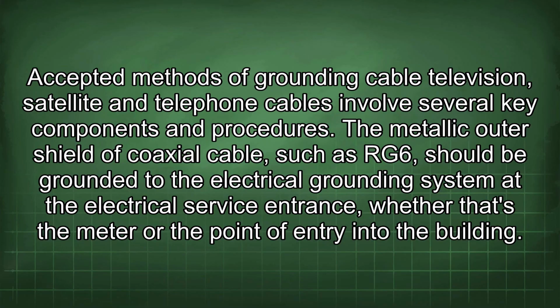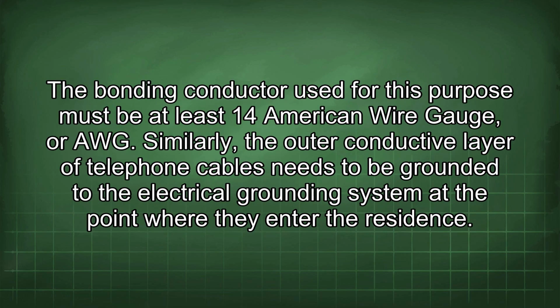Accepted methods of grounding cable television, satellite, and telephone cables involve several key components and procedures. The metallic outer shield of coaxial cable, such as RG6, should be grounded to the electrical grounding system at the electrical service entrance, whether that's the meter or the point of entry into the building. The bonding conductor used for this purpose must be at least 14 American wire gauge, or AWG. Similarly, the outer conductive layer of telephone cables needs to be grounded to the electrical grounding system at the point where they enter the residence.